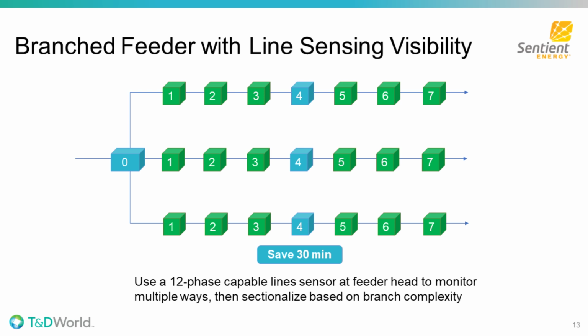Okay, so what we've got here is a branch feeder, and the first order of business with line sensing is to put some visibility into cabinet 0, right? And this is where the circuit branches. And you're going to need a 12-phase line sensor at cabinet 0 to monitor all the phases coming in and out of that cabinet. And then once you've got that, now your crew is going to know which branch of the feeder has the fault.